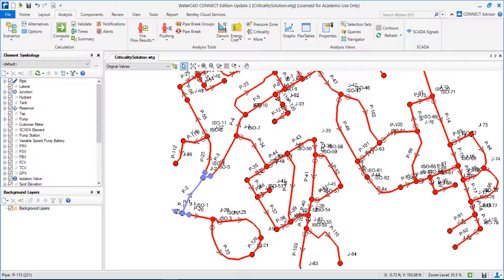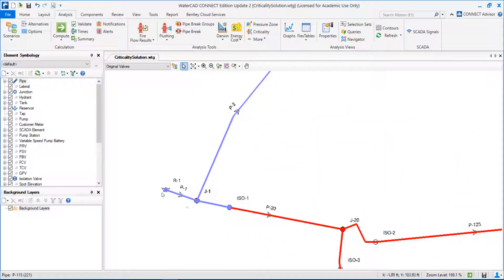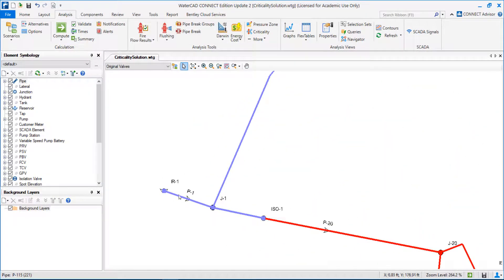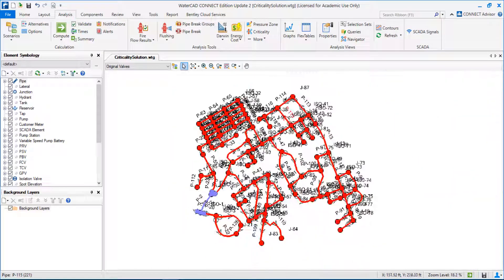In this case, if I need to close this segment, all my network will be affected — all my customers will be without water during this intervention. Why? Because I'm closing the segment downstream, the source of water, downstream reservoir one. In this case, it's difficult to avoid this.